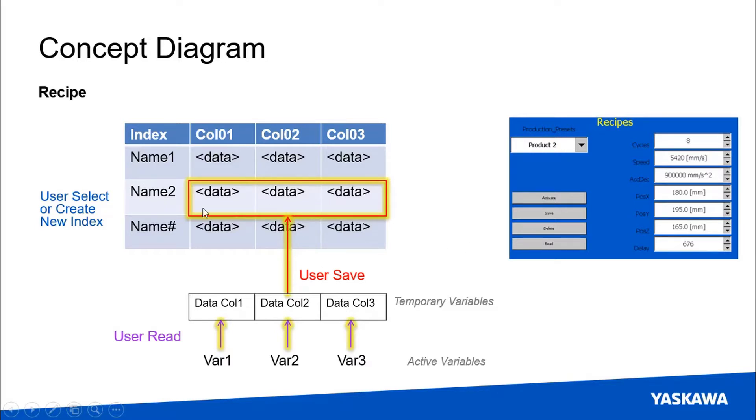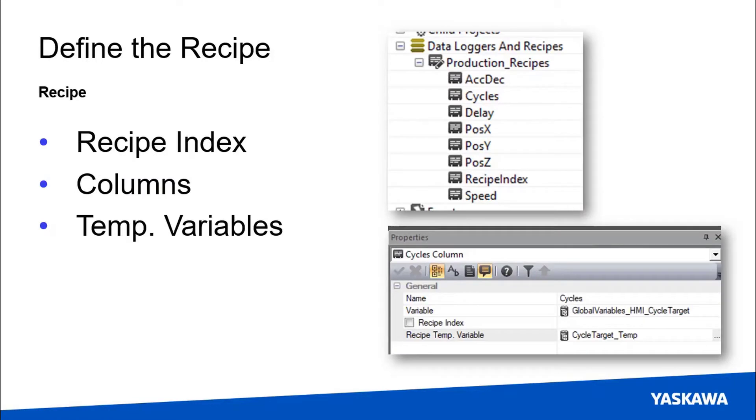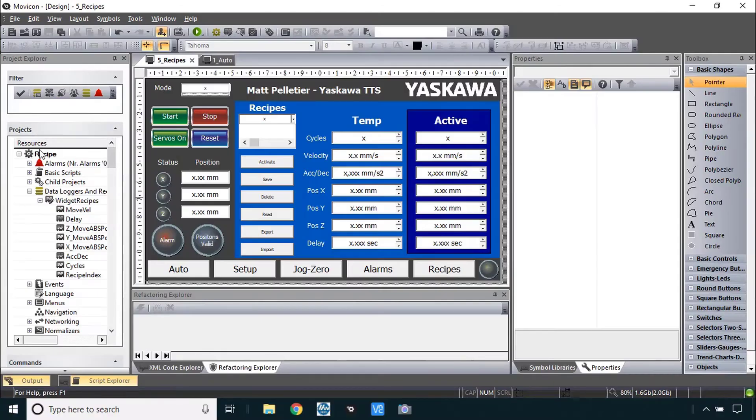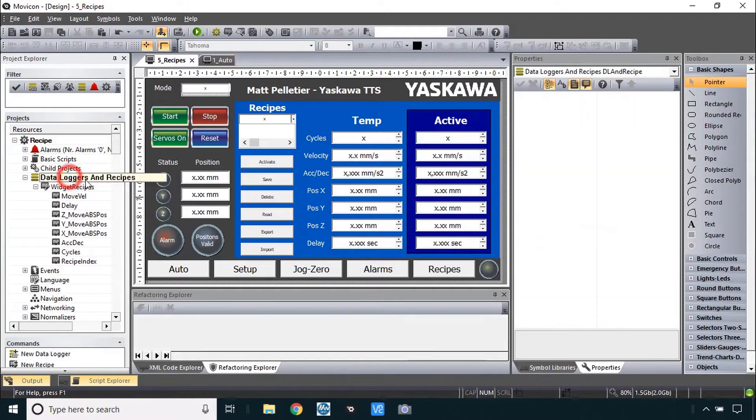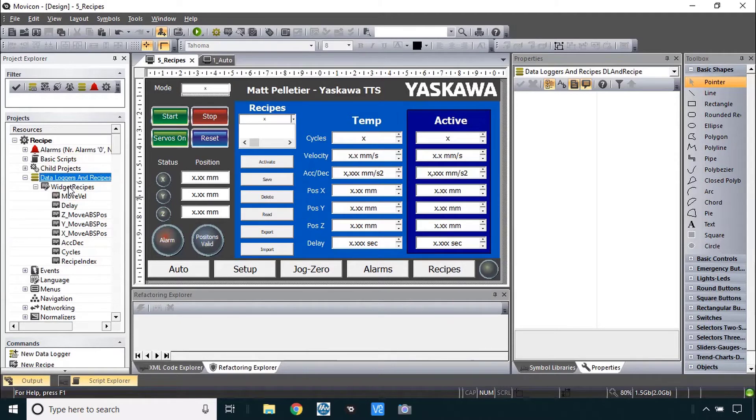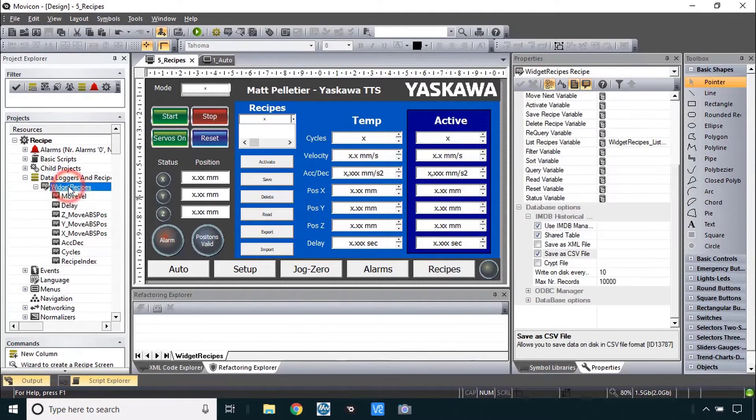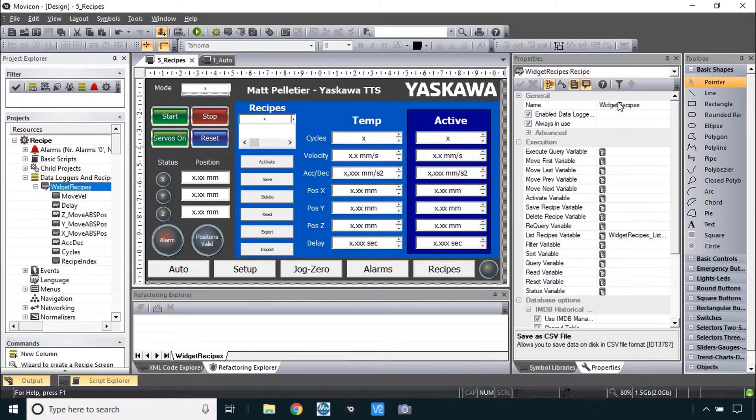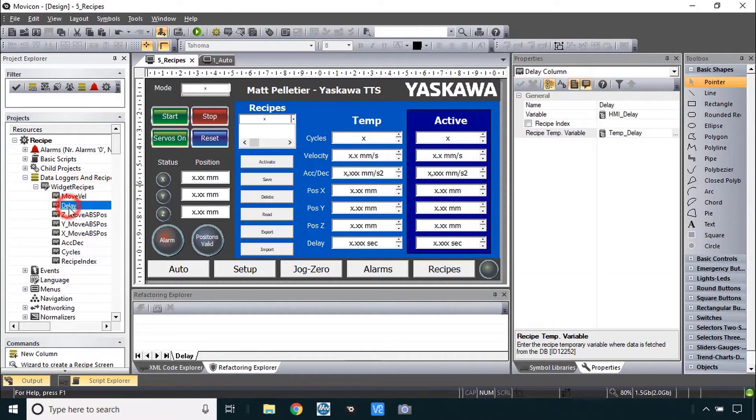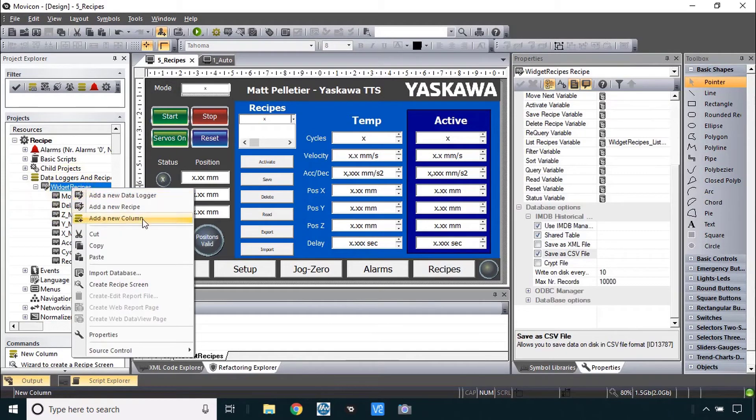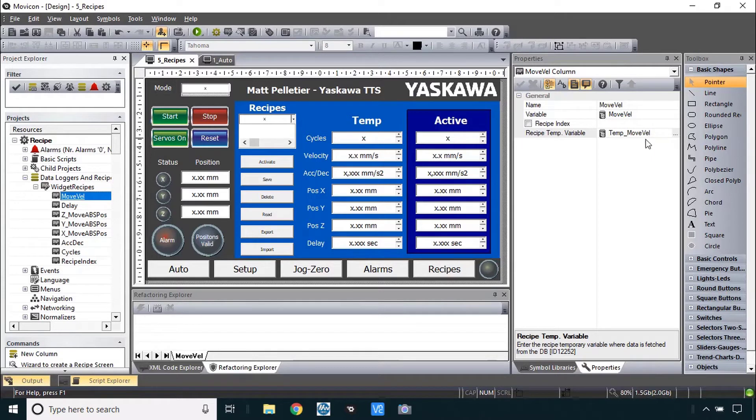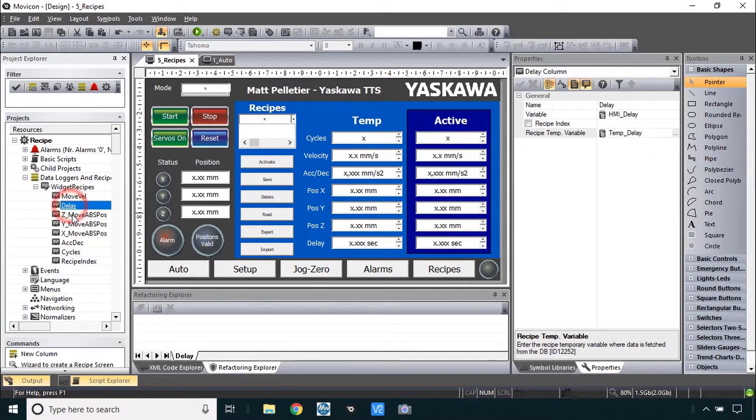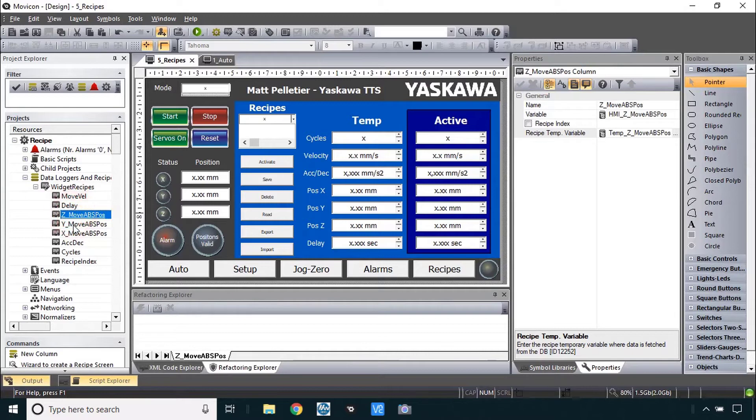In a similar way the active variables can be read into the temporary variable area and then with the save button they're saved into that row of data. Now I'll show you what's happening at the HMI editor level. At the project explorer level you have the name of the project, data loggers and recipes is the area. You'll add this recipe and name it and then individually add each of these columns of data. It's literally called add a new column. So each of these is a column with the active variable and that temp variable that you saw.